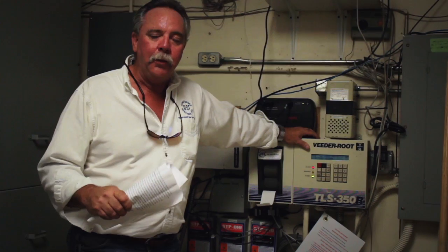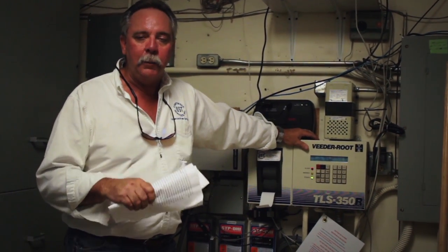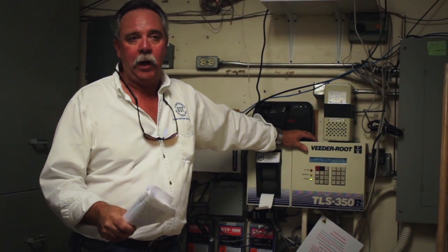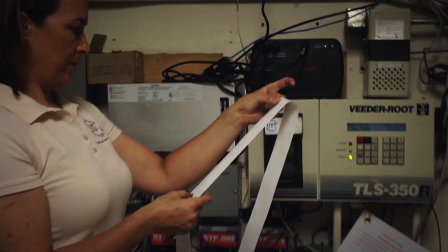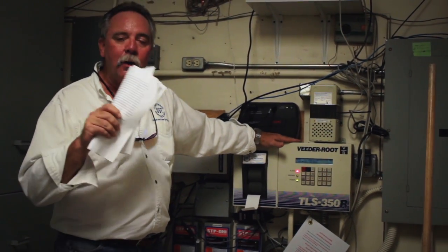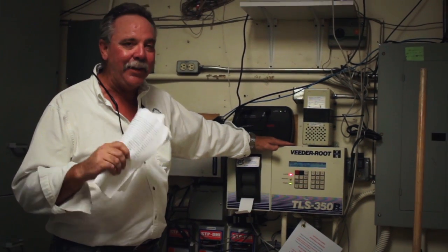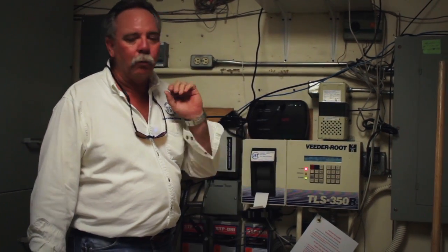When an environmental health inspector comes to this facility to do their inspection, one of the most important things they're going to be checking is that log and the history of alarms that have happened on this monitoring system. Fines can be as high as $10,000 a day for tampering with monitoring equipment, and tampering with monitoring equipment can take many forms in an inspector's mind. If this isn't logged properly, right away you're off on the wrong foot with this inspector. That log is critical. Every alarm needs to be logged.